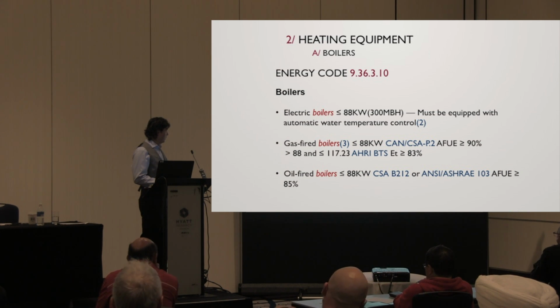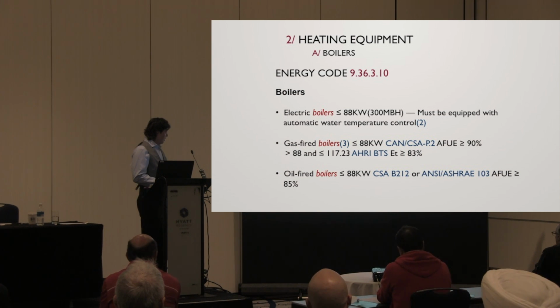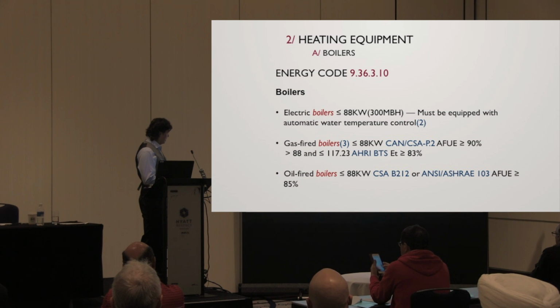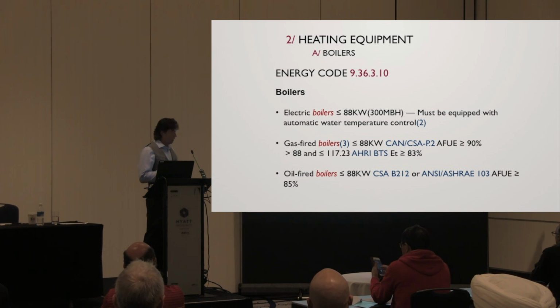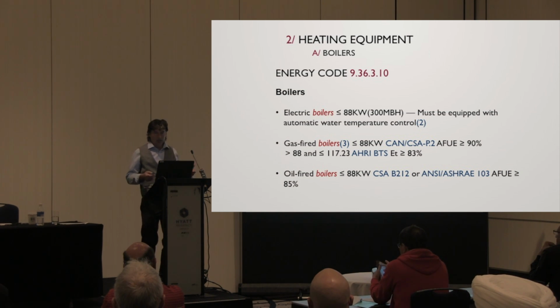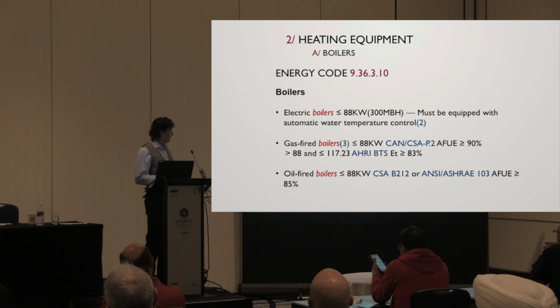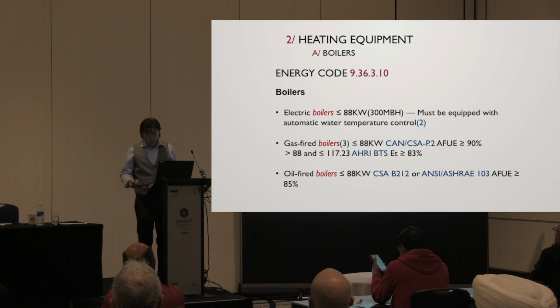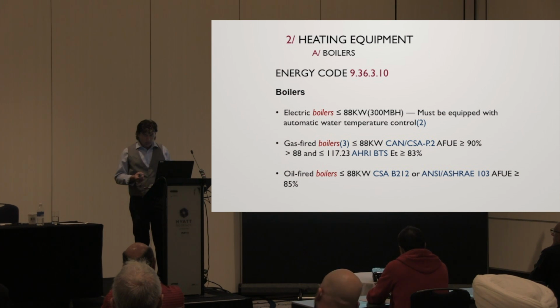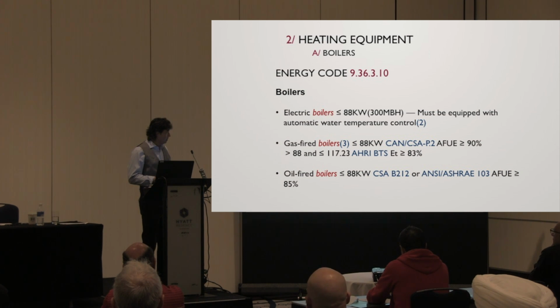Gas-fired boilers, less than 88 kilowatts: AFUE of 90%. And if you're over 300,000 BTUs, you're down to 83%, which is non-condensing. I don't know if you guys know, but any condensing appliance is going to be over 89%. So what they're saying is we want you to use a condensing appliance and we want it to be at least 90% efficient. If you take a condensing boiler and tie it onto a radiant floor where your return water temperatures are very low, you can run up to 98% with a lot of the products available right now. So 90% could indeed be the low end.